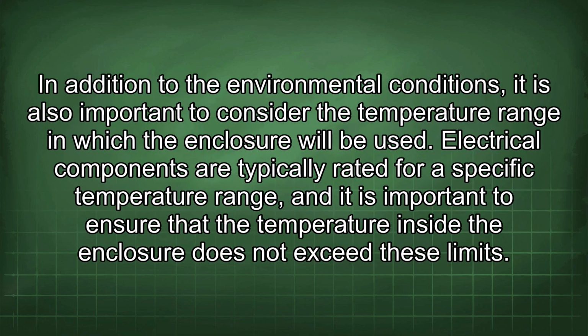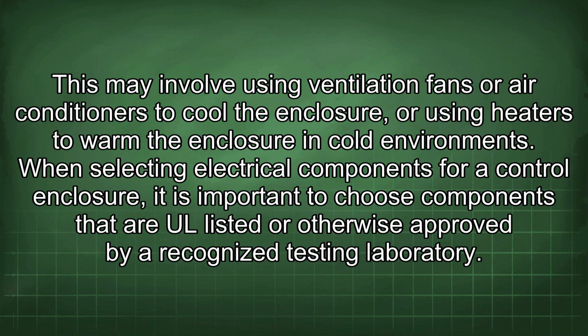In addition to the environmental conditions, it is also important to consider the temperature range in which the enclosure will be used. Electrical components are typically rated for a specific temperature range, and it is important to ensure that the temperature inside the enclosure does not exceed these limits. This may involve using ventilation fans or air conditioners to cool the enclosure, or using heaters to warm the enclosure in cold environments.